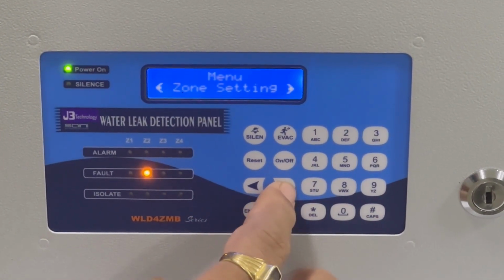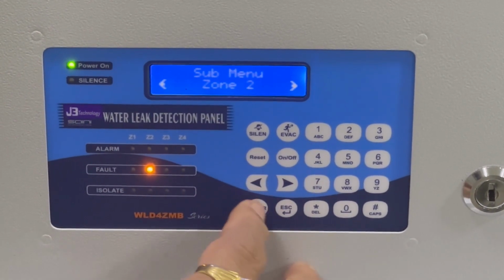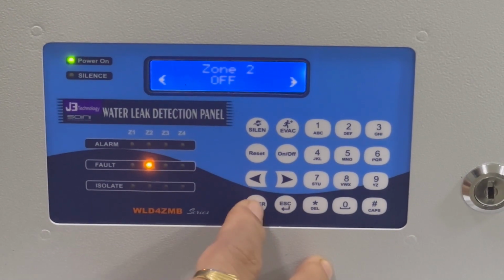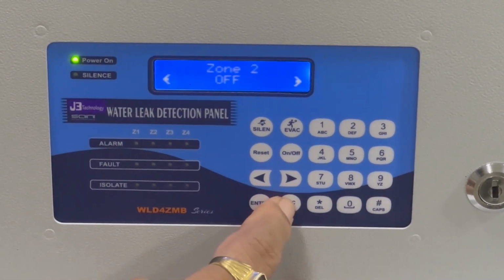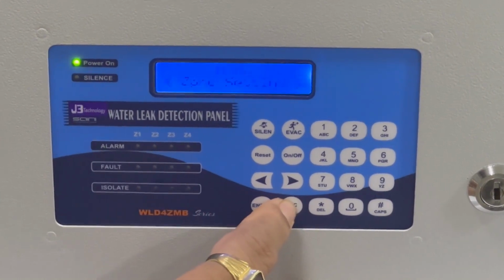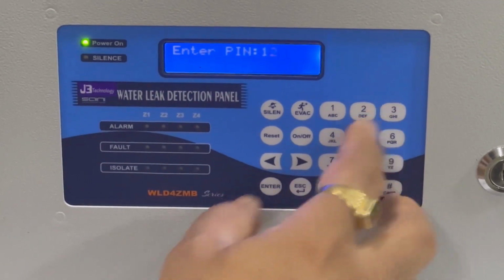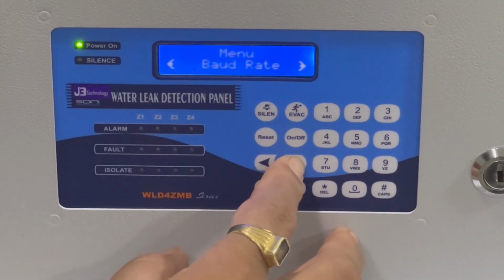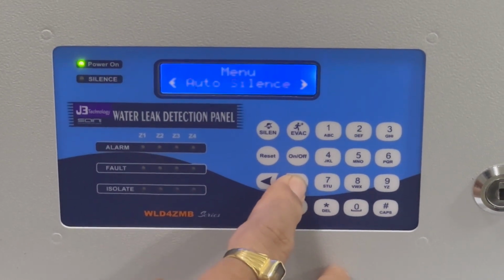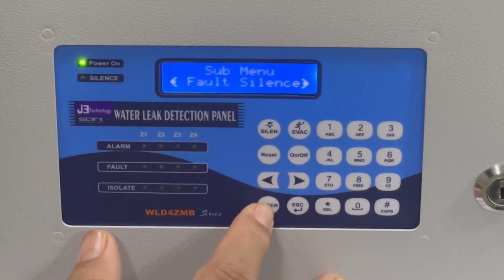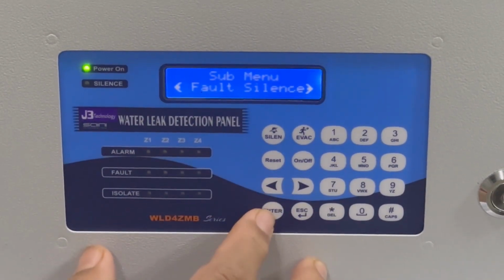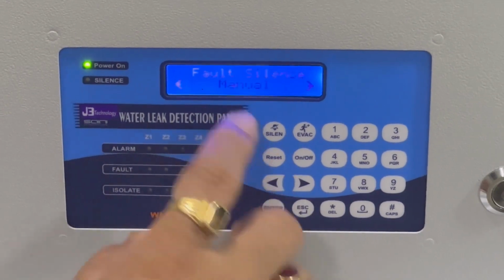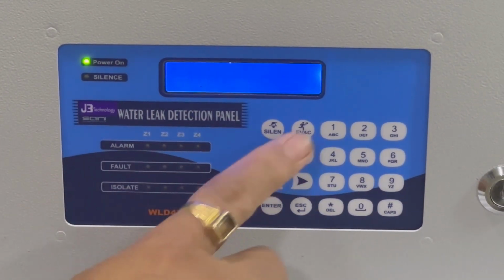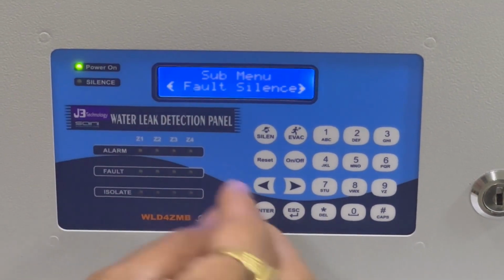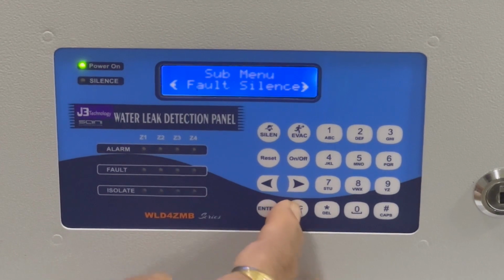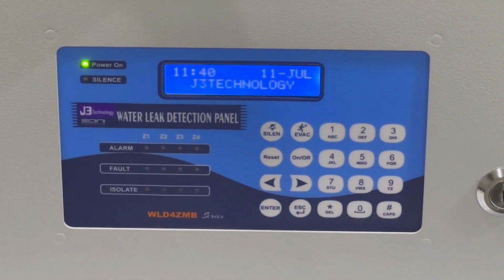Again I put this zone in off mode. The fault will go away. The fault has gone. The main purpose of telling these things is that for auto silence you can define the time until when the buzzer will beep. For fault silence, the buzzer will beep for whatever time you defined, or you can set it to manual also. If you set it to manual, it will continually beep unless you come and manually silence the panel, or it will not silence automatically.